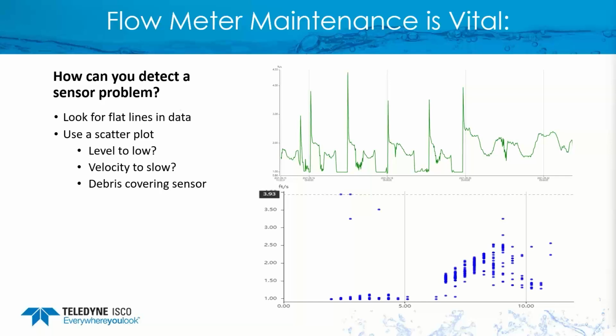Now, depending on your equipment, you may have it set to either interpolate velocity below a certain level, or if it goes into error, you can have it go to 0, or you can hold on to the last known reading. So in this case, the flat lines here are it holding on to the last known reading. Another way to determine that you may be having problems is if you use a scatter plot, you start seeing what some people call corn rowing, an indication that it was just holding on to that last known reading, giving us those values for the velocity. So even though level was changing, it maintained that same velocity reading.